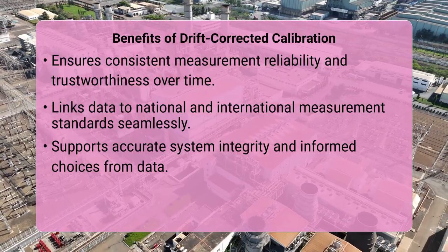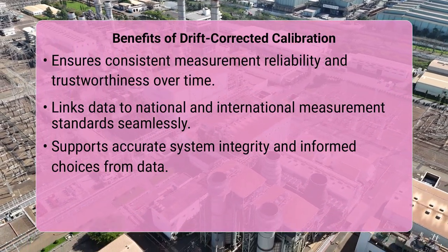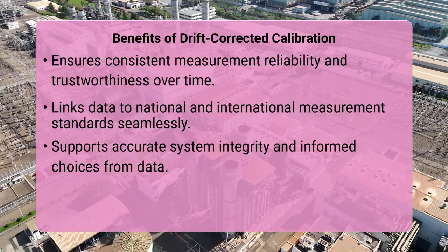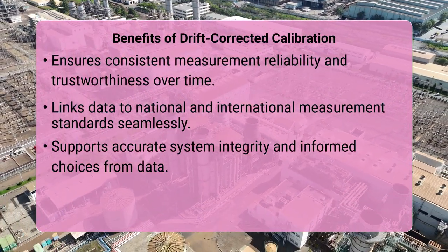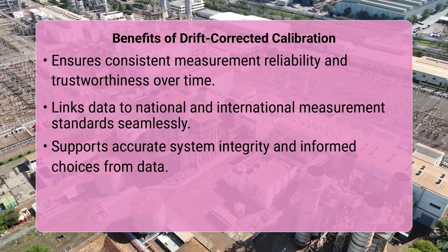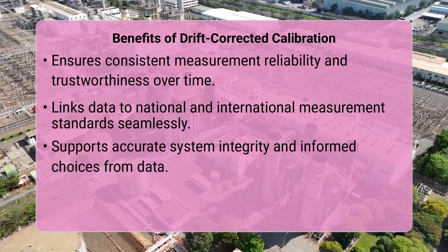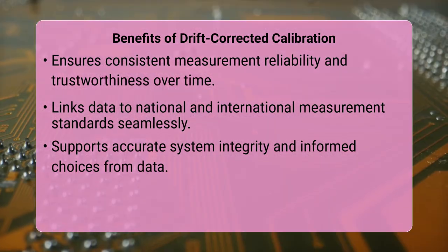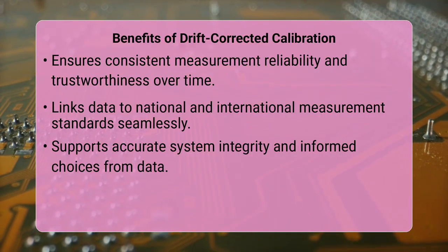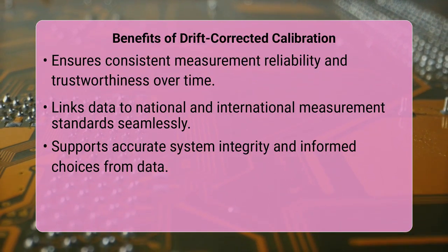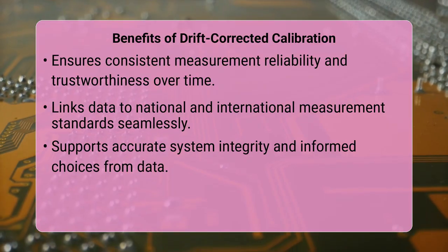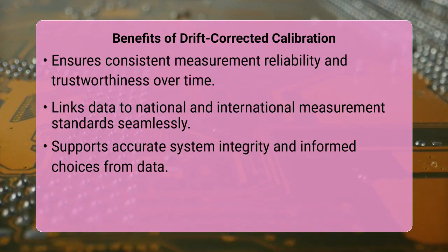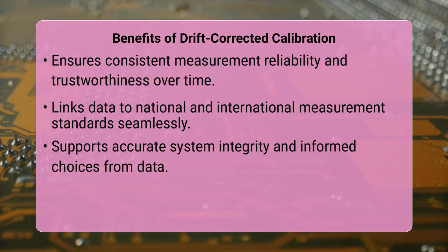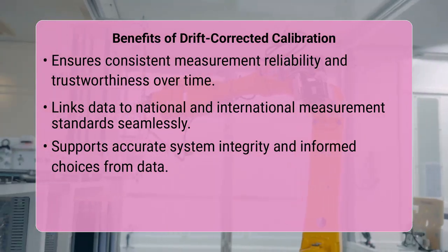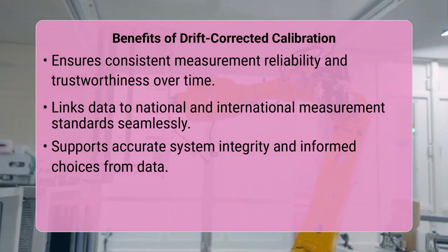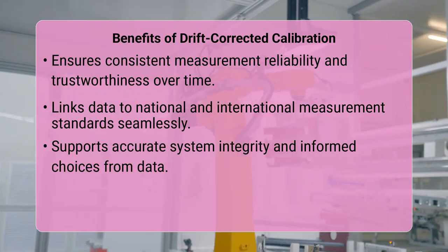By integrating comprehensive drift correction directly into the calibration process, we proactively counter the inherent aging and environmental effects that impact sensors. This strategic approach ensures that the measurement data generated remains consistently accurate and dependable. Ultimately, this empowers reliable decision-making, safeguards the integrity of critical systems, and upholds the overall quality of results throughout the entire operational life of the sensor.